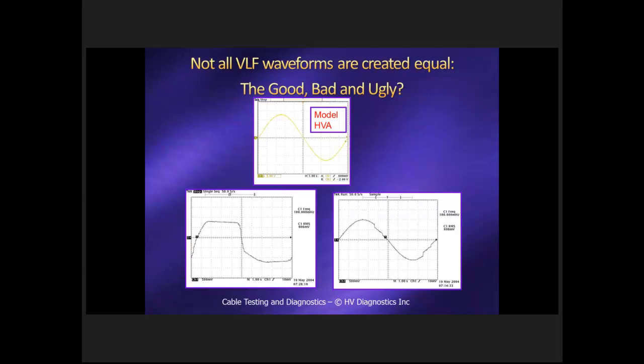It's important that you try and get a good, clean sine wave when you're doing partial discharge in the field. It may not be important if you're doing purely a withstand test to have a perfectly good sine wave, but it certainly becomes important from a noise point of view if you're doing noise testing, or even if you want to do accurate tan delta testing.